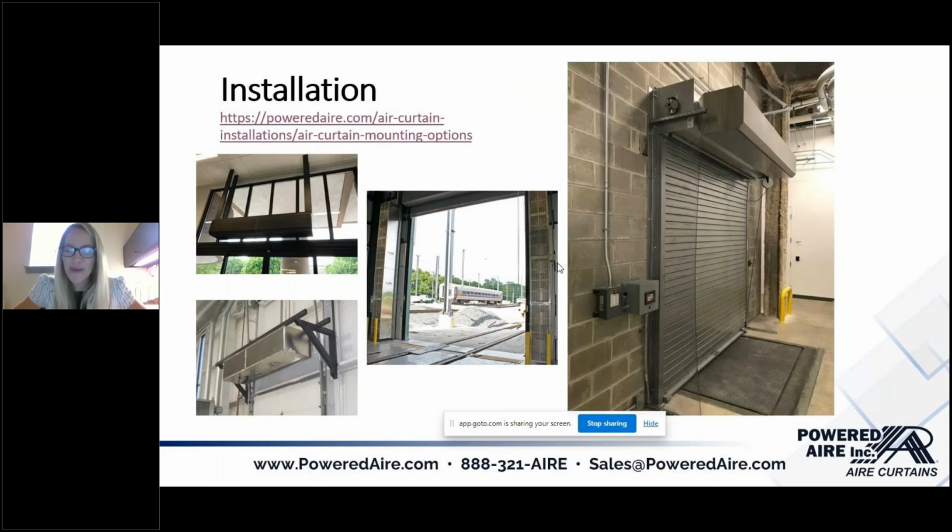Picture on the right, you can't see it very well, but this air curtain is moved out because of the canister. Sometimes if you have to move that air curtain out too far, at the top of the door, you're going to have some infiltration. So we've actually provided PVC side baffles right here. They're clear, so you can't see them that well, but they're there. And that's going to keep that air contained so you do not have that infiltration. So if you are moving the air curtain out too far from the wall, we might want to take a look at these side baffles.